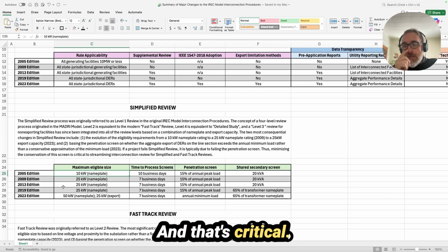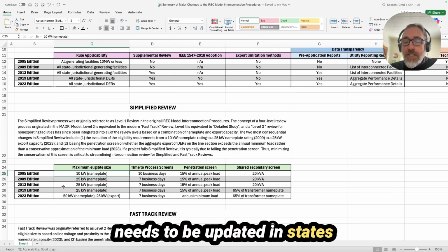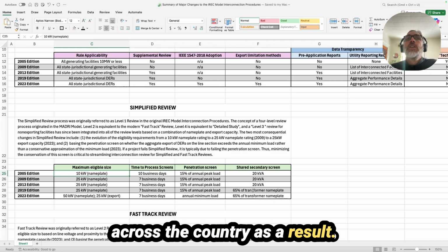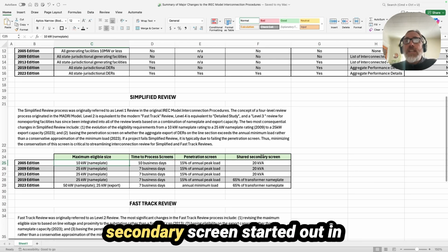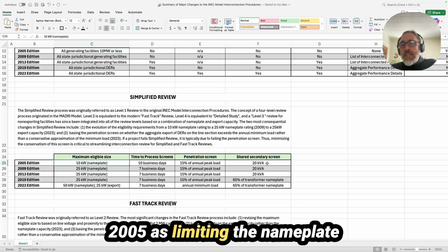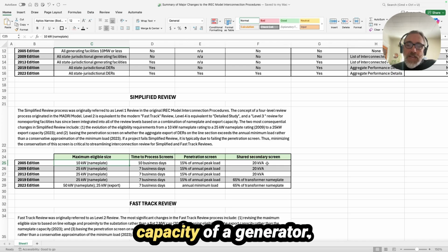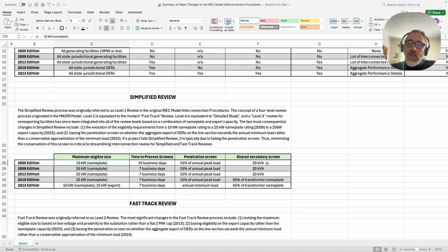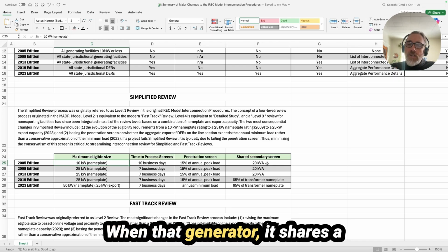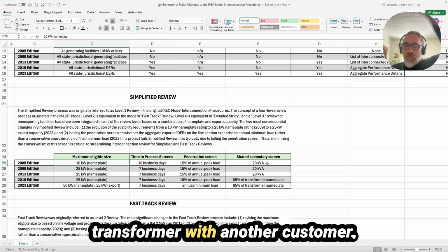And that's critical. And this is a screen that needs to be updated in states across the country as a result. And then lastly, the shared secondary screen started out in 2005 as limiting the nameplate capacity of a generator when that generator shares a transformer with another customer.